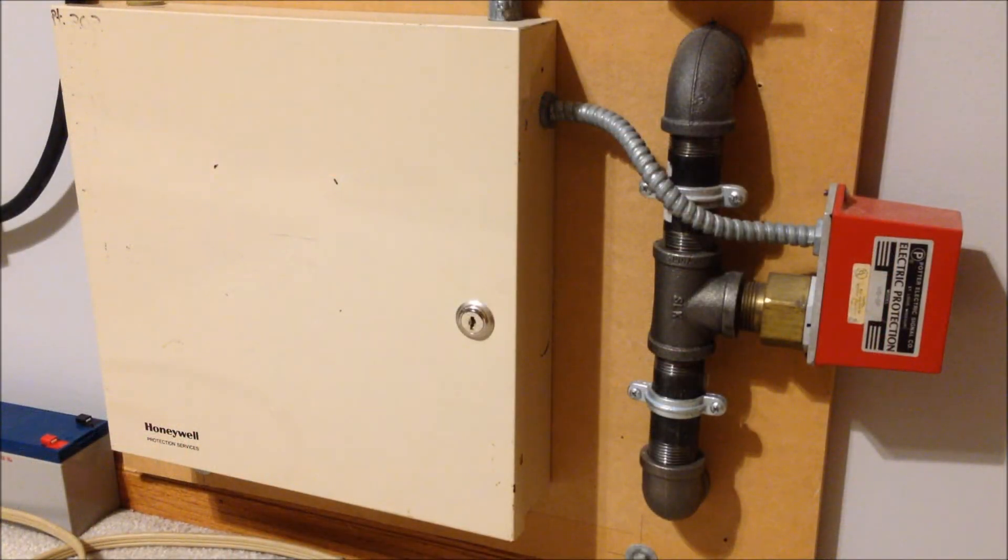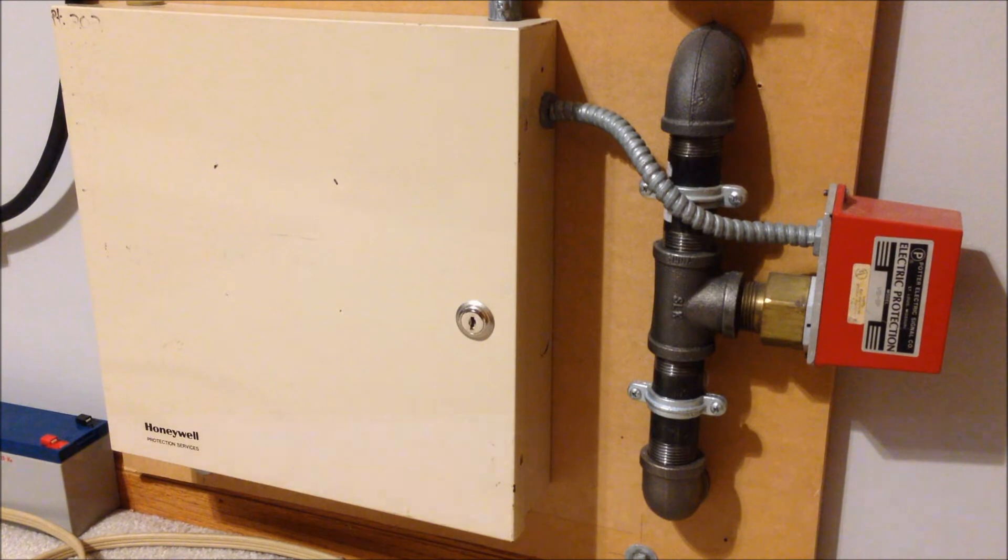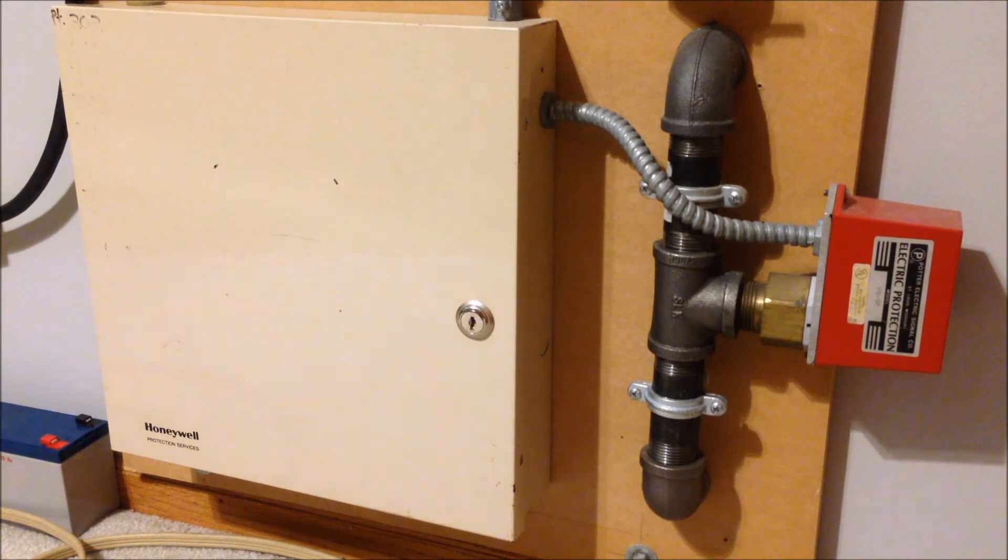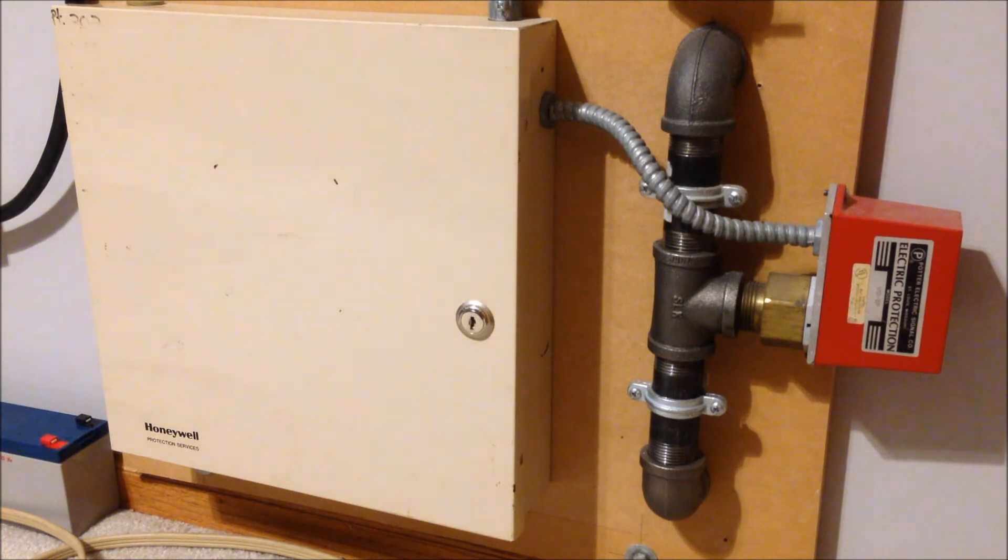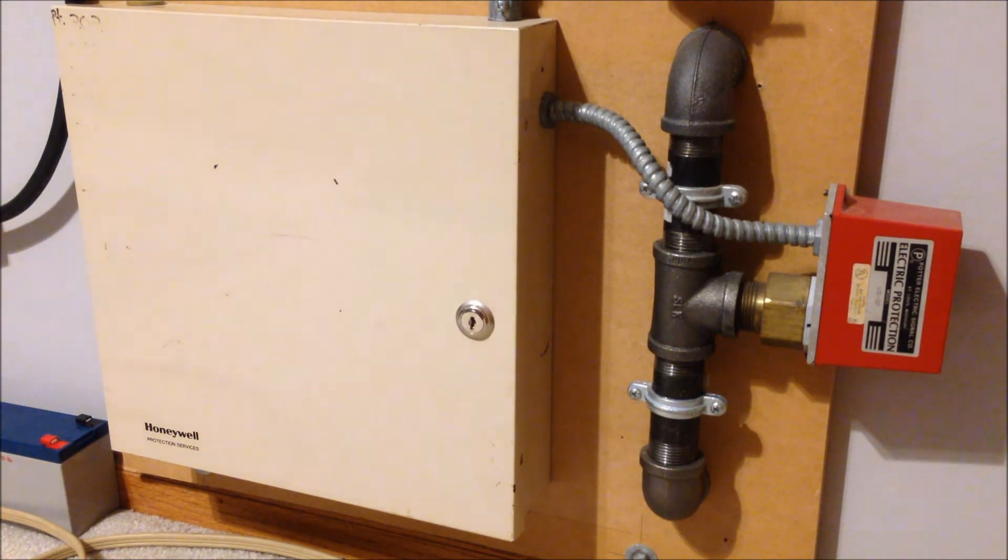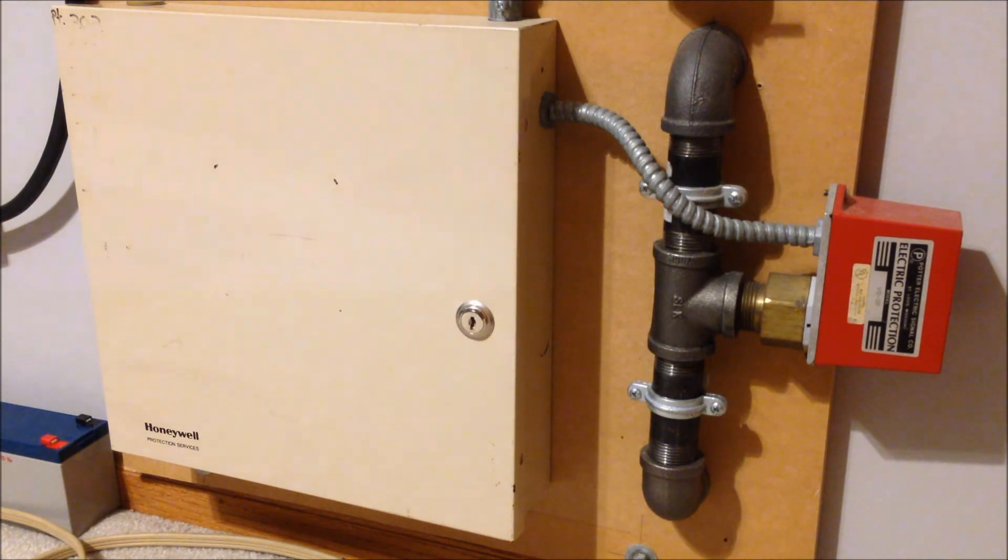So I just realized that I actually don't have my security Torx screwdriver with me to open up the cover on the water flow switch and activate it. So I'm actually going to have to pop open this Honeywell cabinet here and manually activate the Radionics module that it's wired into.